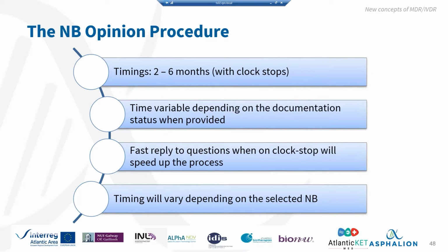Please take into account that when you're assessing or certifying a device, you can select a notified body from among those that have been pre-designated. You can see in the NANDO database which notified bodies are assessing devices depending on the kind of product. So once you identify which would be suitable for your kind of product, you can select between the possibilities. But obviously, there are certain notified bodies that can work faster than others due to their pipelines or efficiency.